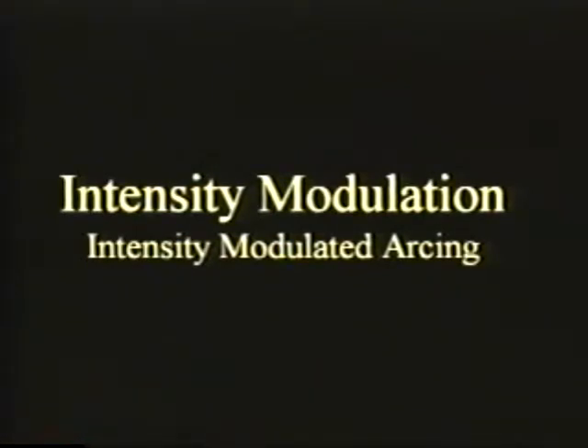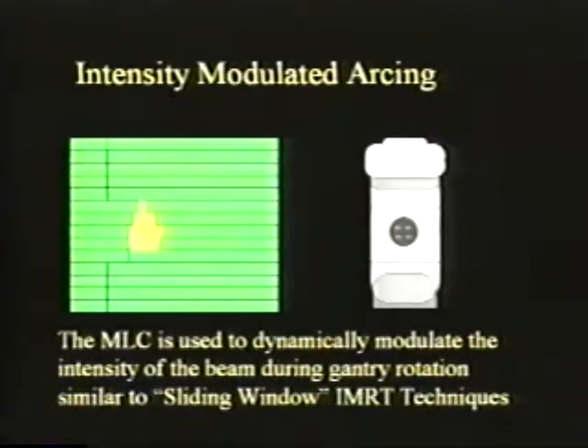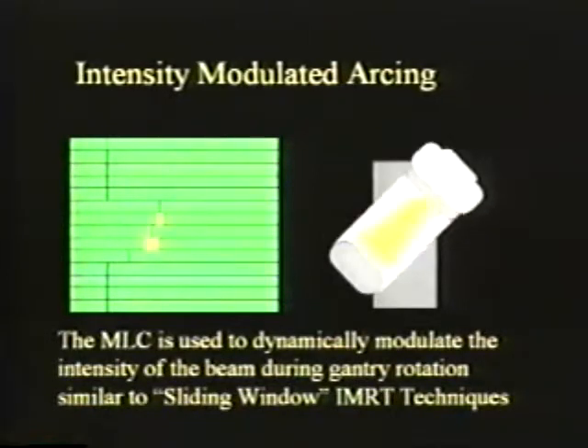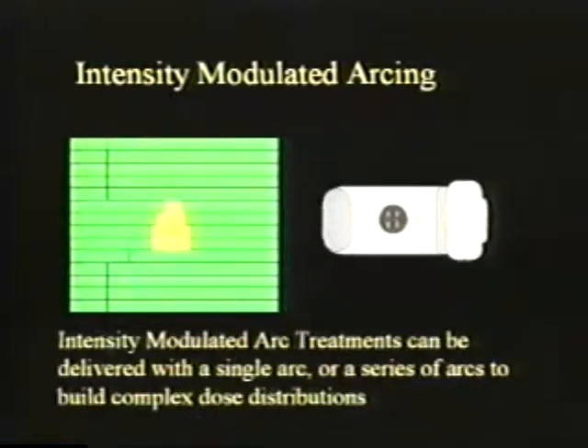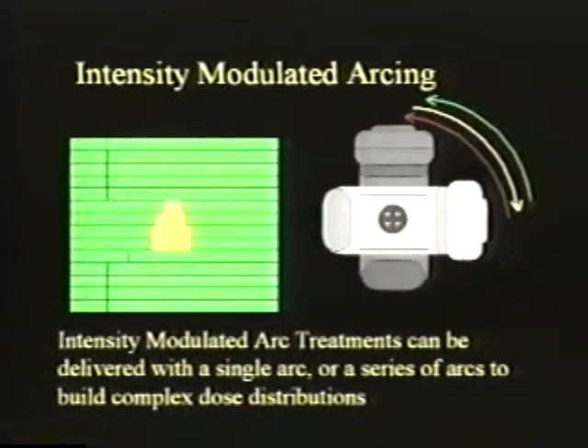Of all the techniques for intensity modulation that I've talked about so far, intensity modulated arcing is by far the most complicated, but it will give you the best dose distributions. In intensity modulated arcing, like conformal arcing, the radiation beam is on and the linear accelerator is rotating. But instead of conforming to the shape of the target, the leaves modulate the intensity during gantry rotation, similar to that sliding window technique that I talked about earlier. And this delivery can be done in either a single pass arc or multiple pass arcs going back and forth over the same area to build up a specific, very complex dose distribution. In the computer animation that I showed at the beginning, where it was sculpting in the granite, it was this type of technique that was being used.